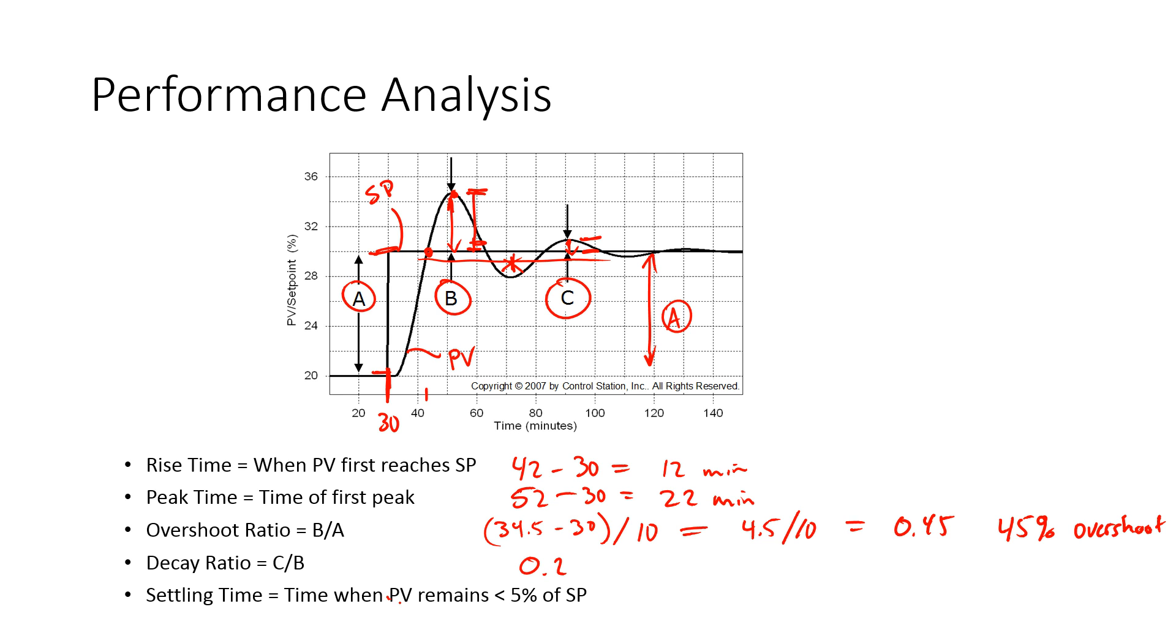Settling time is when the PV remains within 5% of the set point, now 5% of the delta. So take your A and go 0.05, and then you draw your bounds here, and when this PV stays within that, the first time that it enters that and then stays within that 5% band, that's when we call the settling time.